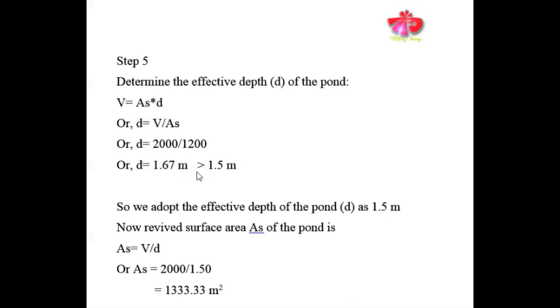Since 1.67 m exceeds the maximum allowable effective depth of 1.5 m, we adopt d = 1.5 m. With this revised depth, we recalculate the surface area: revised surface area = V / d = 2000 / 1.5 = 1333.33 square meters.